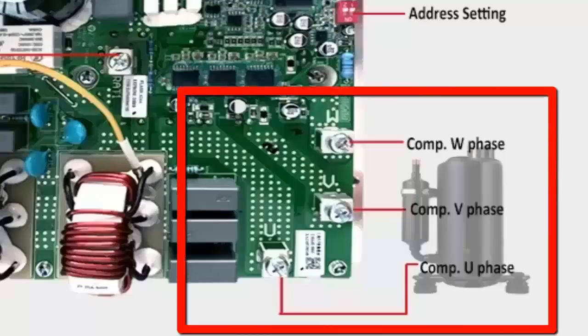Step 5: Identify the output points UVW. These can be identified by following the tracks from the compressor connectors to the IPM electronic circuit.